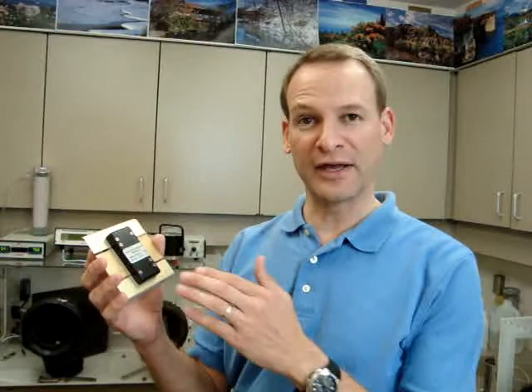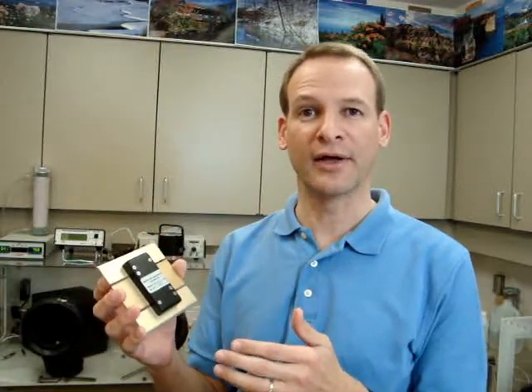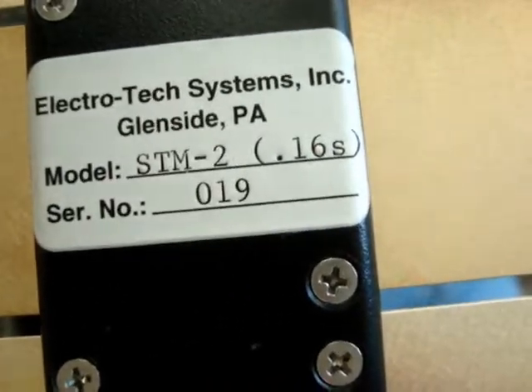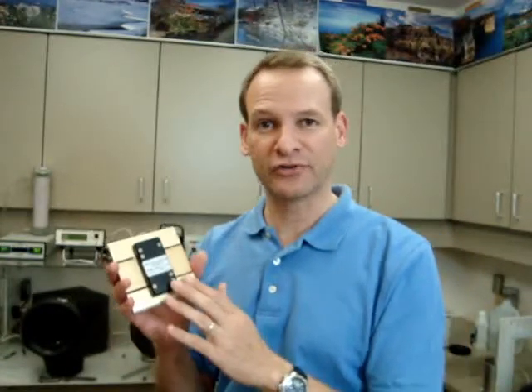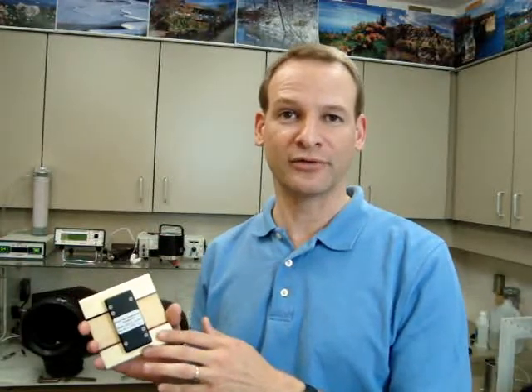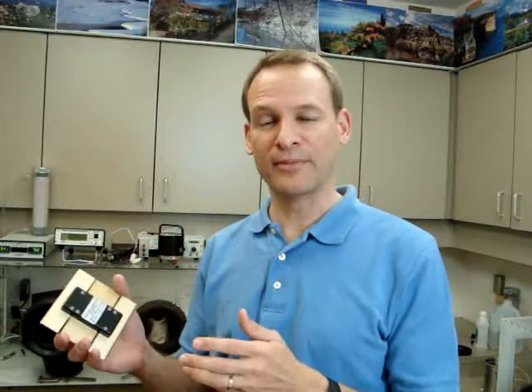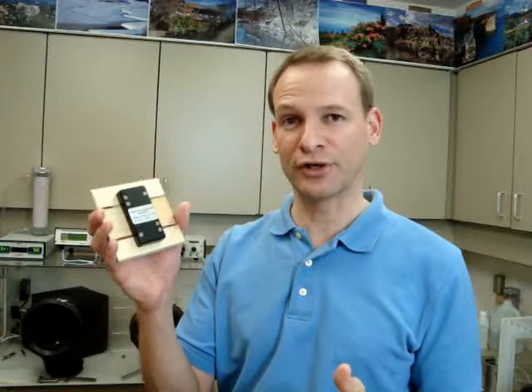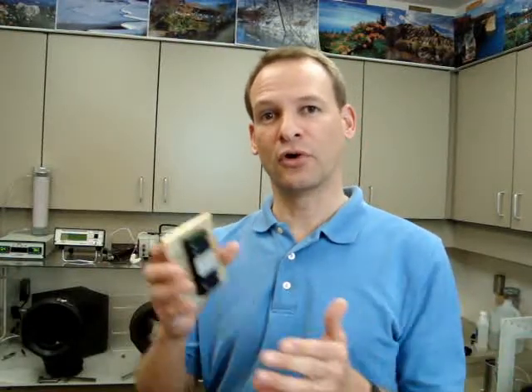So each unit of the STM-1 or 2 is stamped with a reading. In this case, you notice it's stamped 0.16 seconds, which means when you go to test this, you put in the system, you run a test either in positive or negative, that's high voltage, you're going to read about 0.16 seconds. Now, the spec says it can be a difference of 0.05 seconds, plus or minus. So, what that means is you have a range, using this STM-2 in particular, of 0.11 seconds all the way up to 0.21 seconds, because it's stamped 0.16, plus or minus 0.05 seconds.